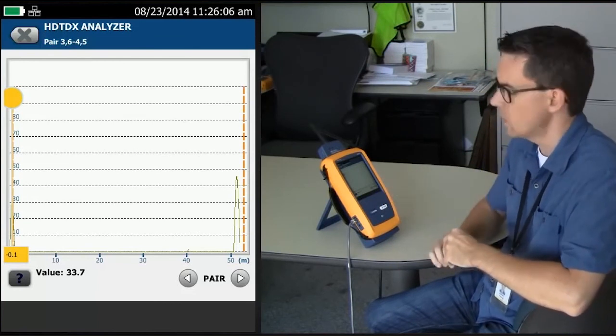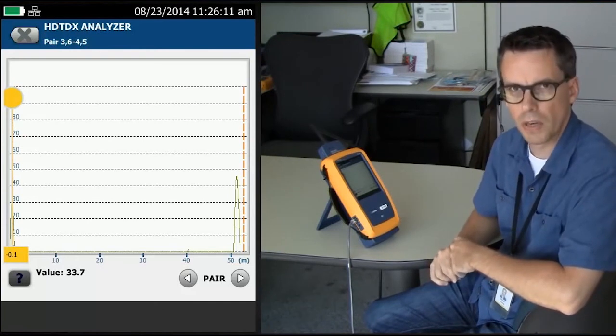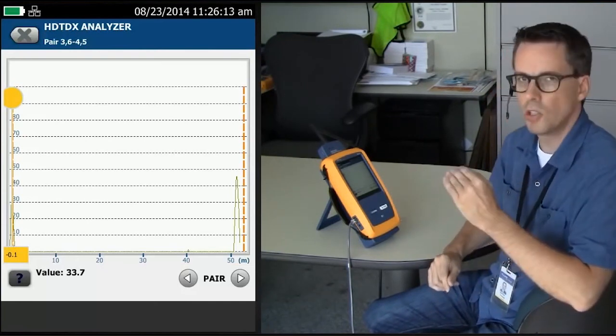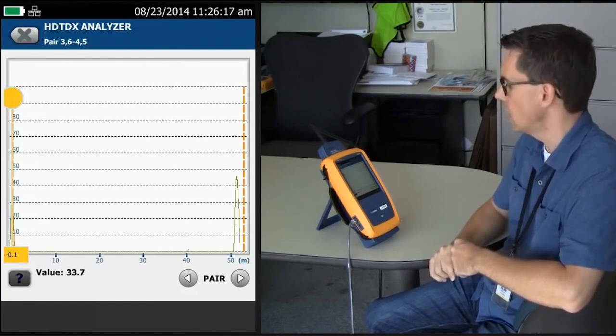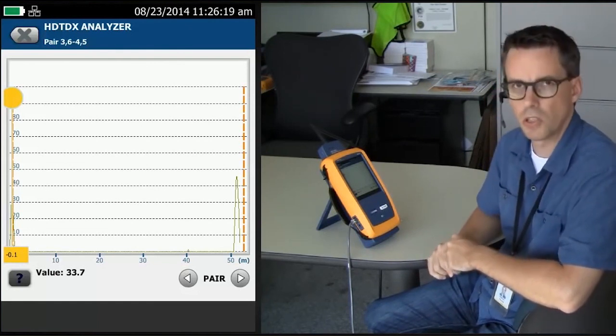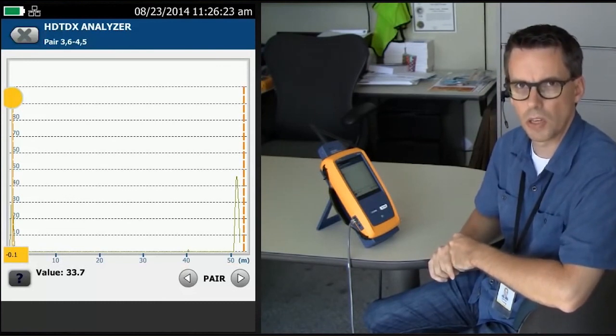The first thing I would do is re-terminate the far end. And, indeed, in this customer, when he re-terminated the far end correctly, the margin came up and he got a very good pass. That is how you diagnose a termination issue on the DSX 5000 cable analyzer that caused a crosstalk issue.